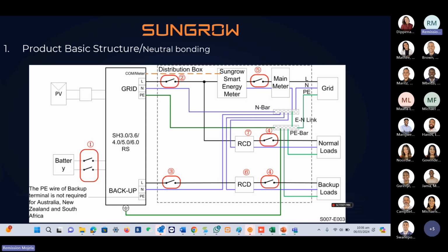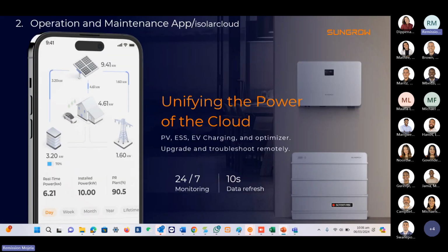So the most important thing is that you can just use a common neutral with the one from the grid before your earth leakages, or bond the neutral to earth before going into the earth leakage. Either way, the neutral should be bonded, or be common with the neutral from the grid, as the South African grounding system is a TN-C-S system, whereby the neutral and earth coming from the municipality or coming from Eskom are already common. So it's already grounded, by the way.